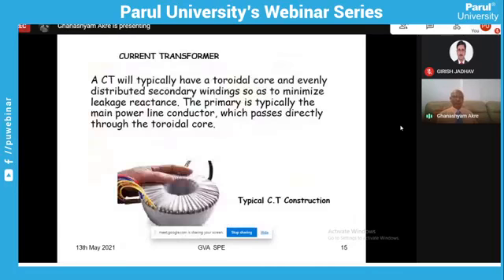In that case, whatever current it draws, that is the magnetizing current, it will be strictly by the property of the material of the core, and not in addition due to impurities like air gaps and other things. So that is why current transformers are always, you will find, in toroidal fashion. This is the shape, the toroid with secondary winding. And the number of turns of the secondary winding can be varied depending upon the ratio.